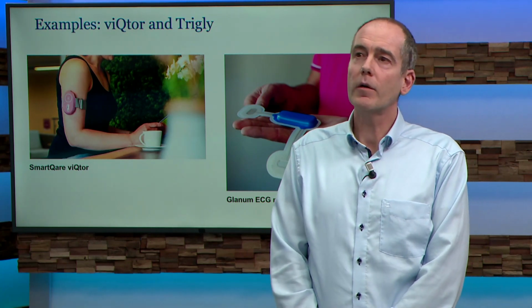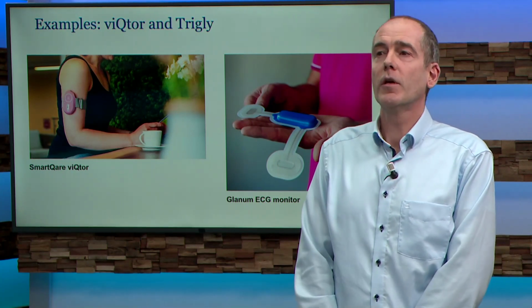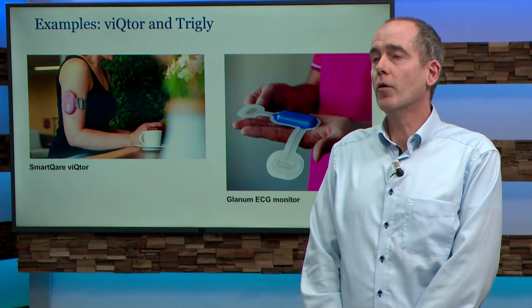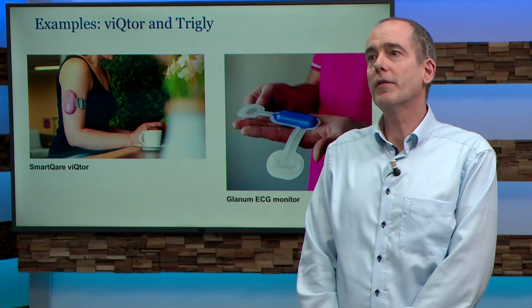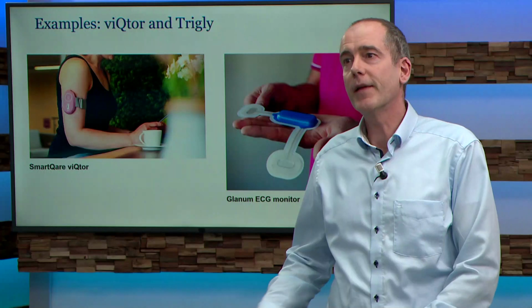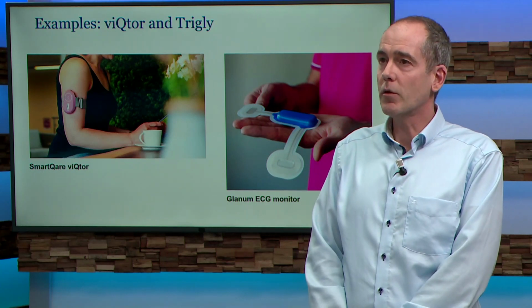Yeah, if you design a product, by the way, minimum viable product is one approach of doing business. In this case, it was selected because we focus on the Holter technology, so ECG registration. The patch has more sensors on board, but they are not used at the moment. And the aim is to develop it, to produce it, commercialize it as soon as possible, and then start working on next generation patches. And for this device, it was feasible.